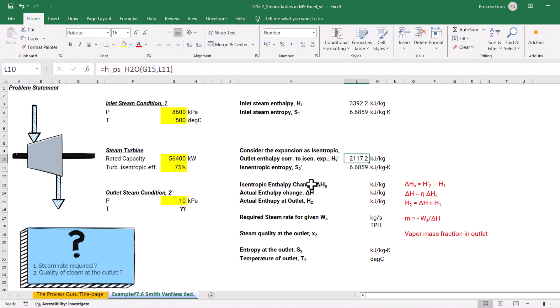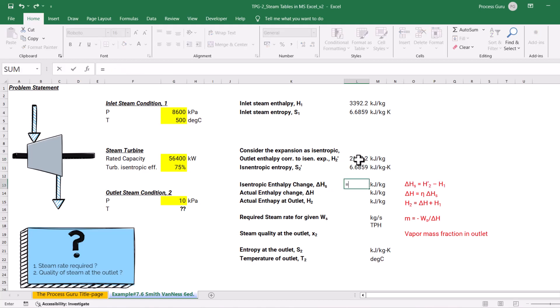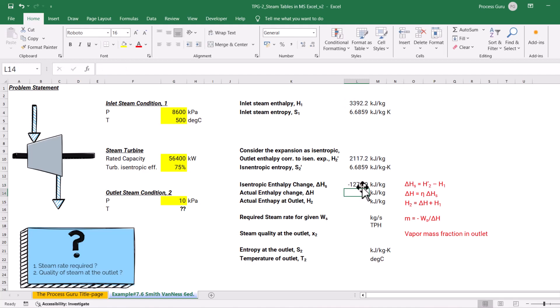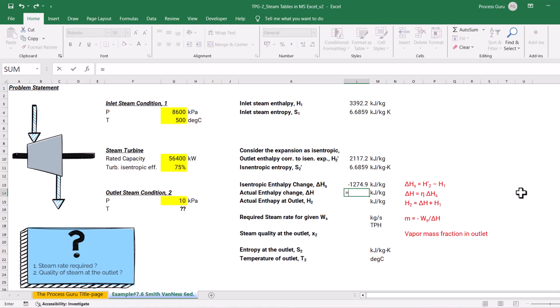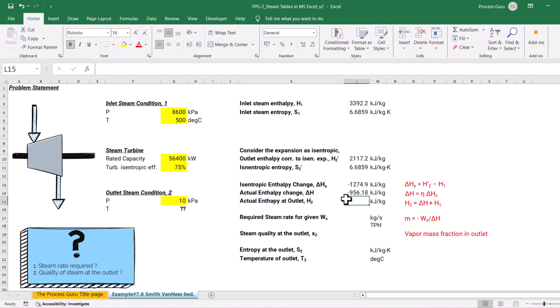Now I calculate the isentropic enthalpy change, which is H2 prime minus H1, giving minus 1274.9 kilojoules per kg. For the actual enthalpy change, I multiply this isentropic enthalpy change by the isentropic efficiency, which gives approximately minus 956.18 kilojoules per kg.